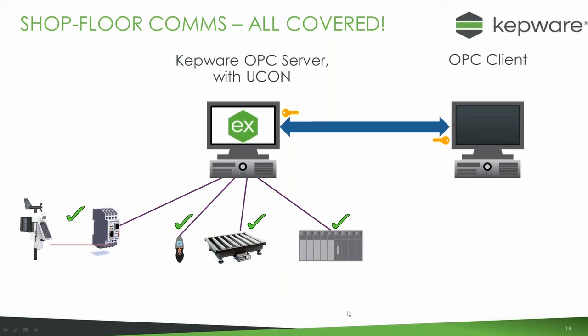With the Kepware UCON server, native serial, Ethernet, and PLC communications are handled by the pre-configured drivers in Kep server, while unusual devices are handled by UCON — including serial devices, Ethernet devices, and serial-through-Ethernet devices using a serial-Ethernet bridge. The bridge accepts communications from Kep server, strips the Ethernet wrapper, and sends the serial communications to the local device. This is particularly useful for legacy devices at the end of a comms link where you'd rather use a local Ethernet connection than run extensive wiring.